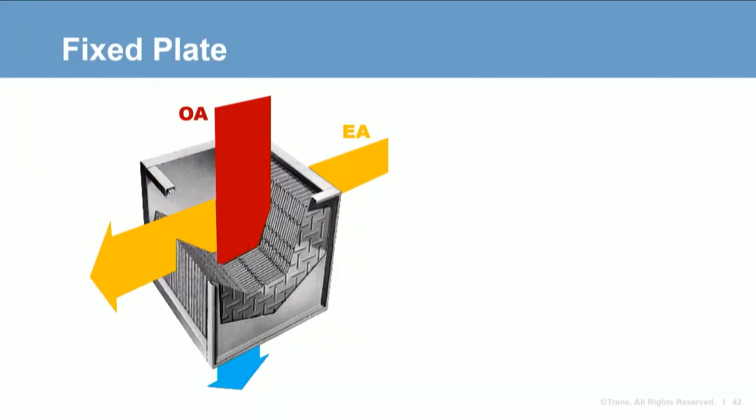The next technology is the fixed plate heat exchanger. It uses a series of plates with internal separators to create independent separate airflow channels. Aluminum is the most common material. The plates and separators are stacked with alternate edges sealed to prevent cross leakage. These exchangers can withstand large pressure differentials — some up to 10 inches of water between sides. Fixed plate heat exchangers can also handle higher temperatures and sometimes have an optional corrosion protection coating.